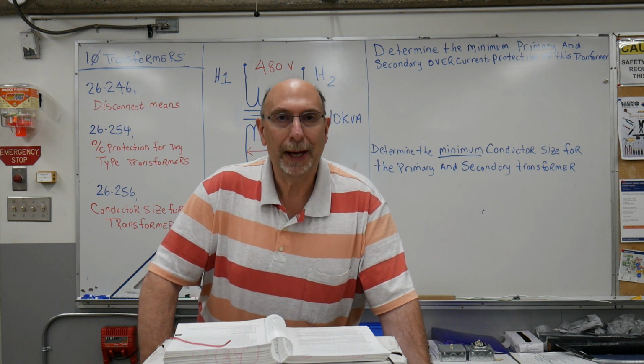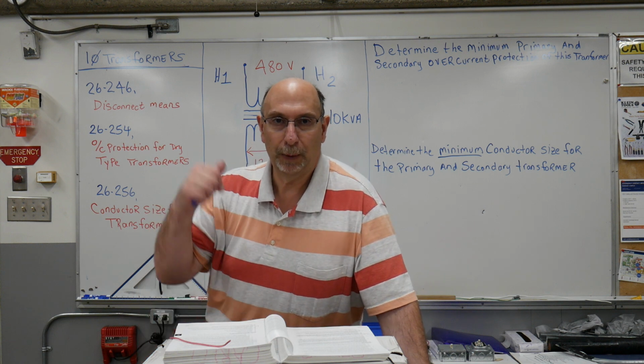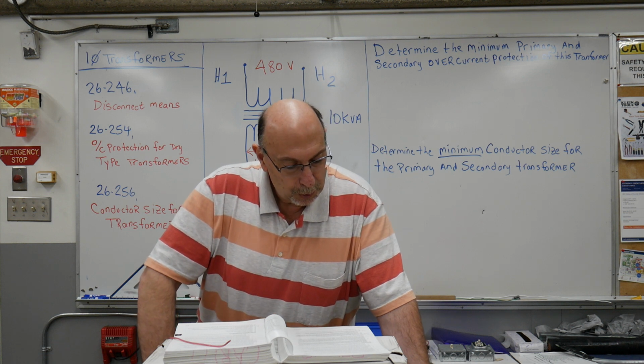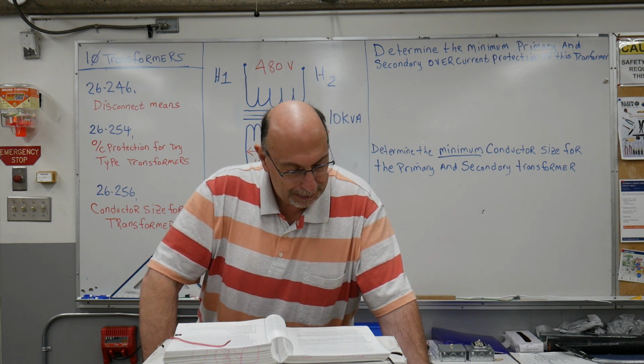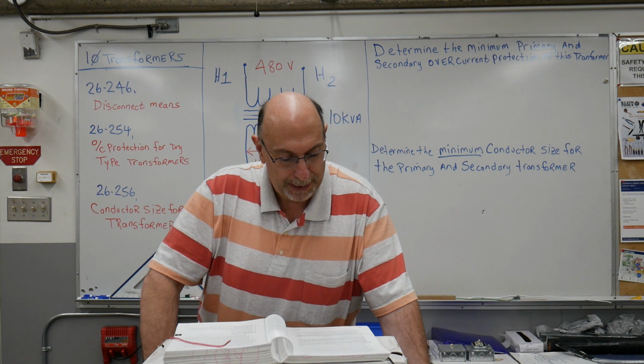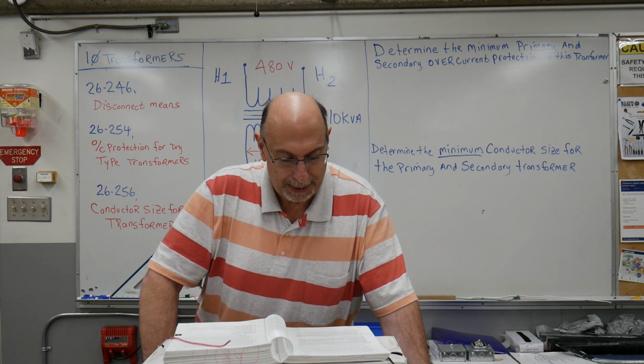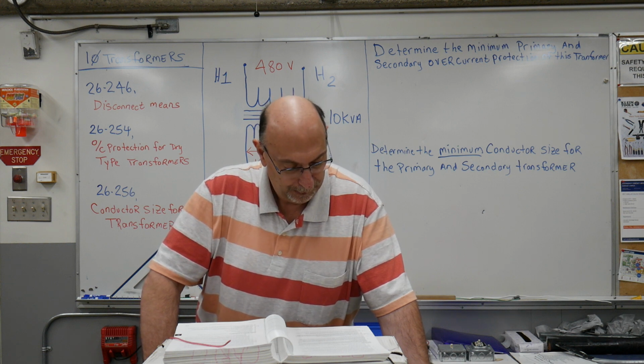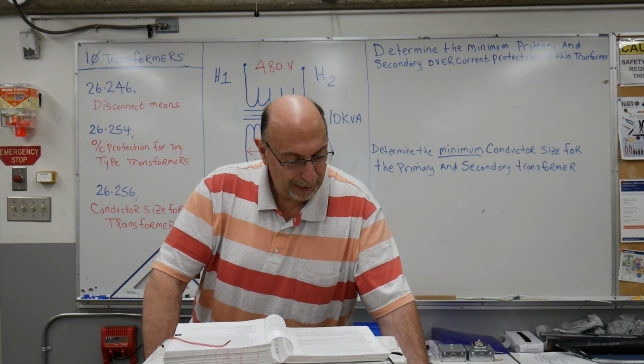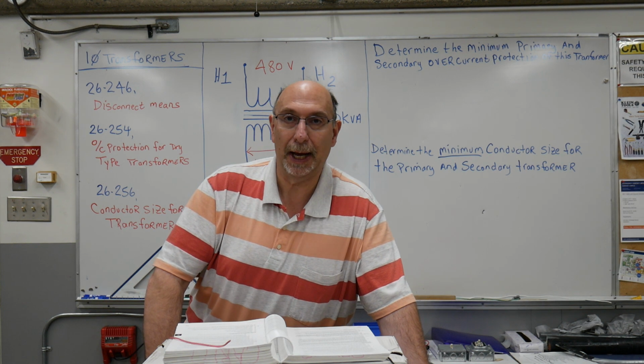I'll go over the rule and then we'll go over this example right beside me. So 26254 talks about overcurrent protection for dry type transformer circuits rated at 750 volts or less. And 26256 talks about the conductor size of transformers.